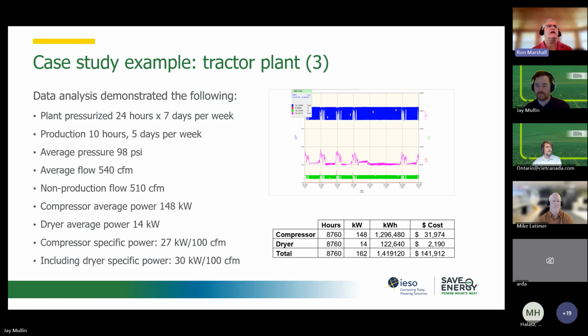So we can see from the characteristic of the flow and pressure and power profile that production is only happening 10 hours a day, 5 days a week. We can see the average pressure, the flow, non-production flow, and that kind of piqued my interest. The difference between the average flow and the non-production flow is only 30 CFM. That's really strange, right? So when there's nothing in the plant, the lights are out, they're still flowing 510 CFM, right?